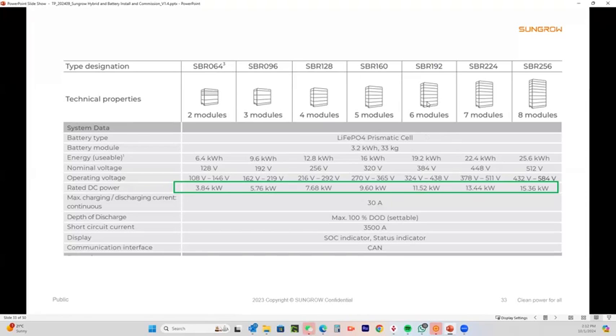So if they are buying 3 modules, just make sure that you don't connect more than that 5.76 kilowatts onto the backup loads, okay? It's fine if there's PV there as well and if there's grid there as well. But at night when there's no PV and if the grid goes off, you are reliant entirely on that battery, okay? So these are the critical things to look out for, cross-referencing it with the inverter. Do the same on the SBH range, okay?